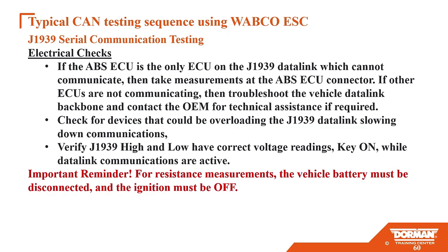Commonalities, okay. Here's an electrical check, this is actual serial communication testing, a good resistance check. The test is checking resistance, network to ground. Connect your ohm meter between the network circuit and a good ground. You should have infinite resistance.